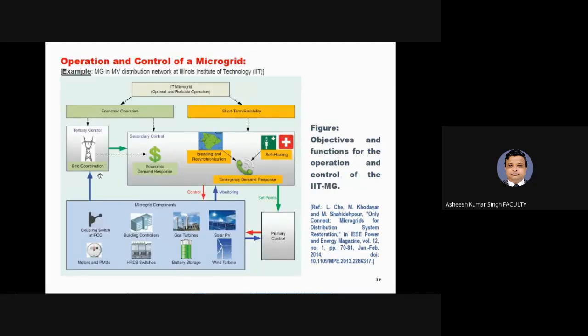And then comes the tertiary control, which manages the flow between the microgrid and the utility grid, and provides optimal scheduling of these DER units and demands for both islanded and grid-connected modes. As I talked about earlier, ancillary services to the utility grid are also provided by this microgrid in terms of voltage and frequency regulation and restoration services.